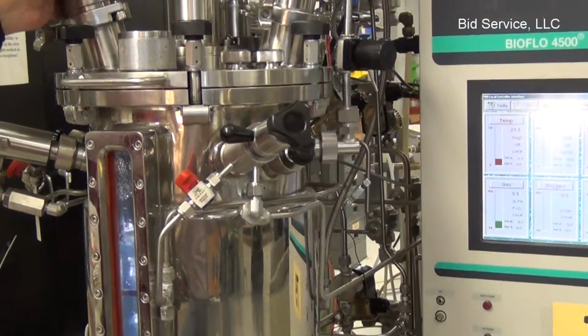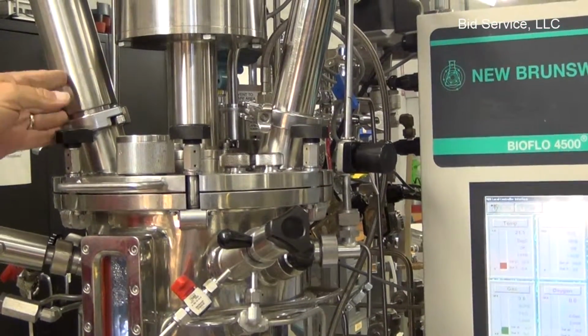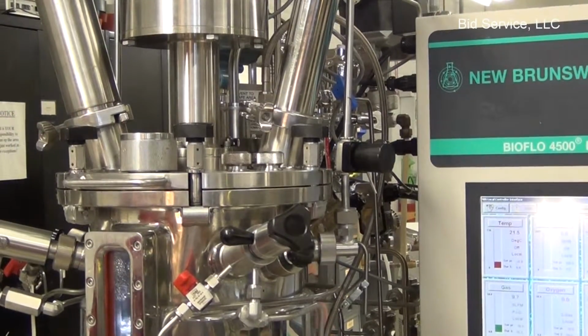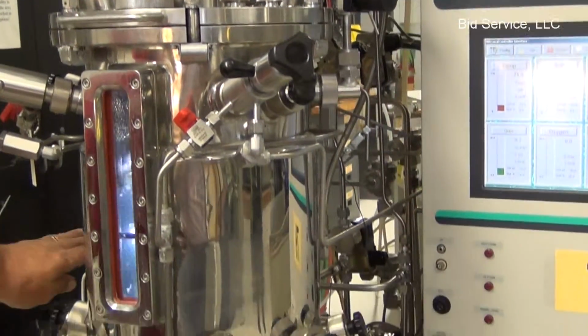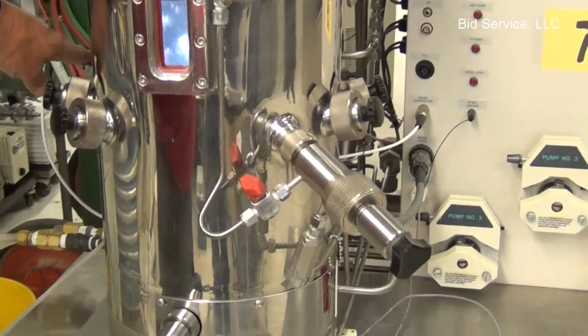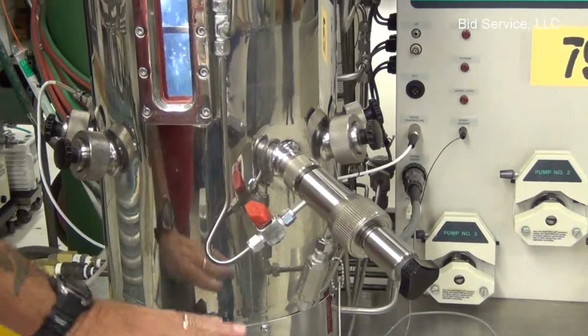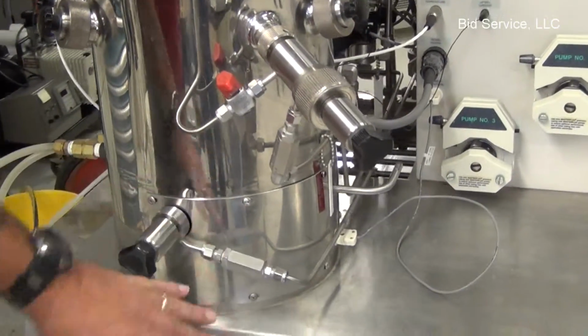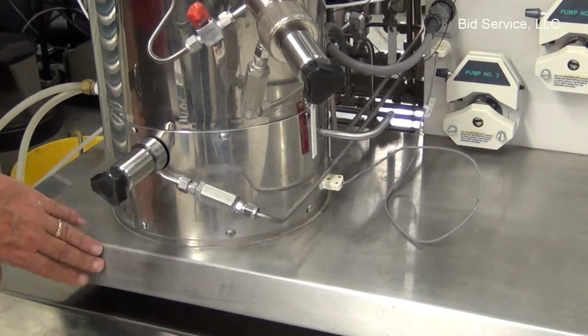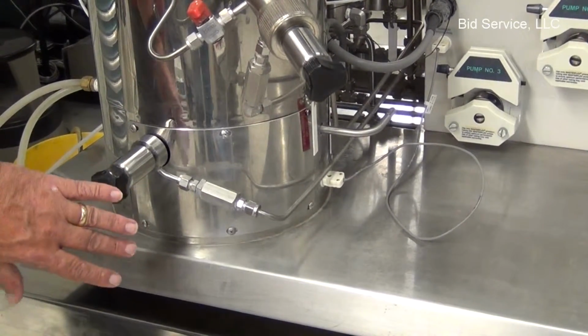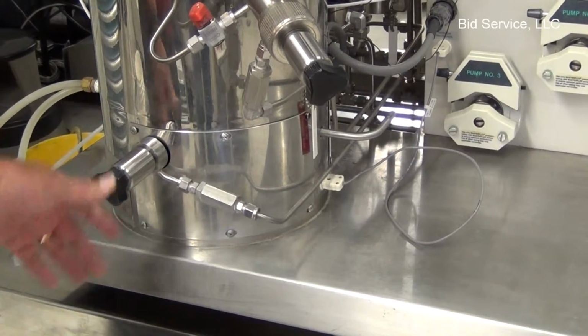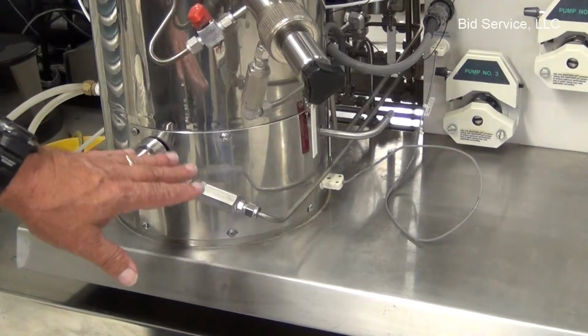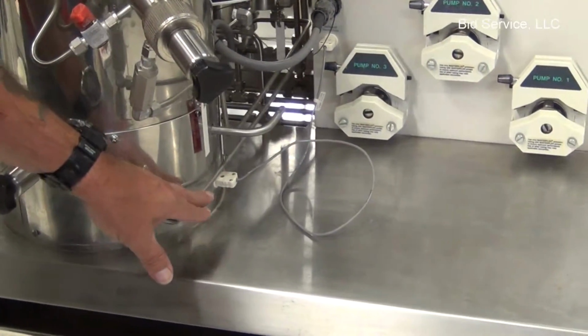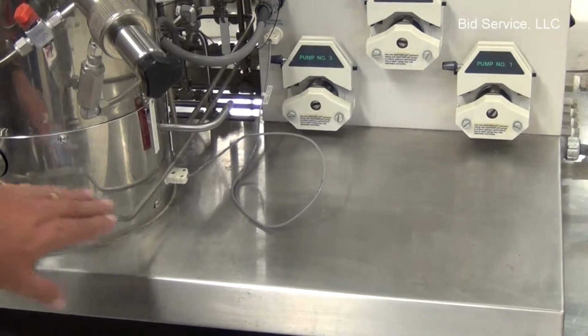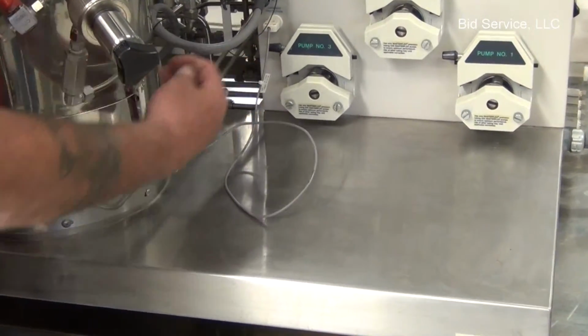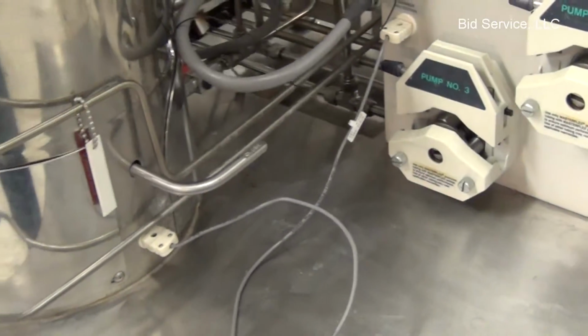Your light is here. This is an LED light that's been added to the system in place of the incandescent bulb that used to get really hot. On the left side here is your temperature sensor, and in front here is your drain. There'll be a trough on the front of this. It's being cleaned. That trough, you can have your effluent come straight out of here and go directly into the troughs. If it's just water or liquid, very thin viscosity, you could have it just go out to the drain via this line, and there is an on and off valve here.